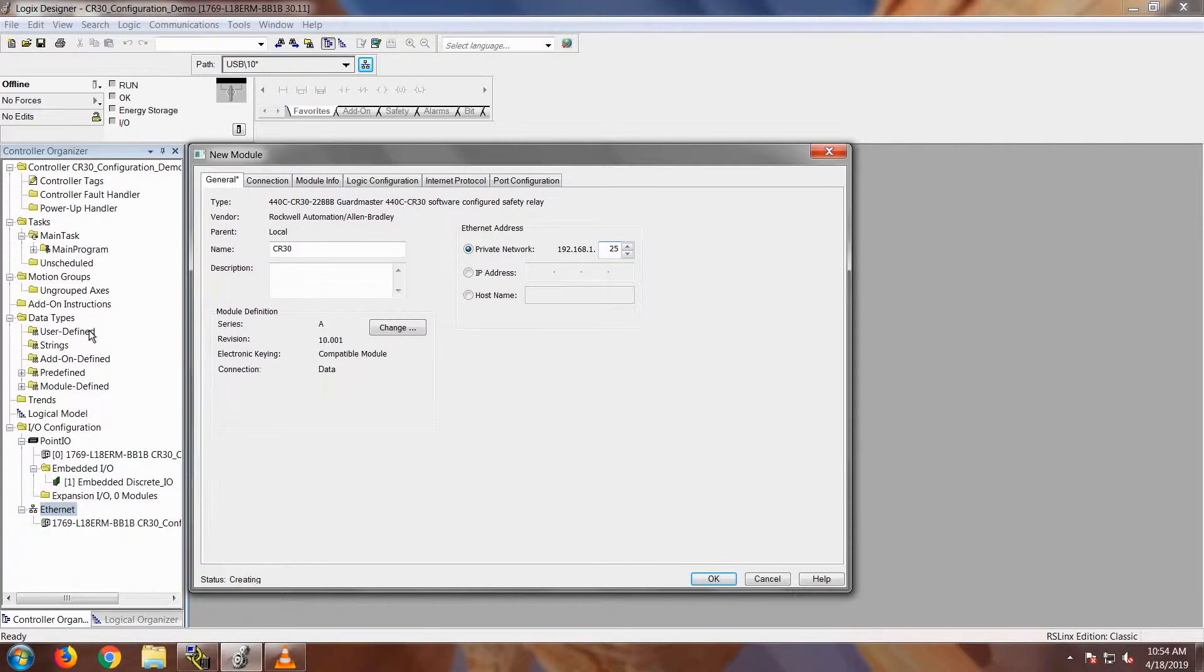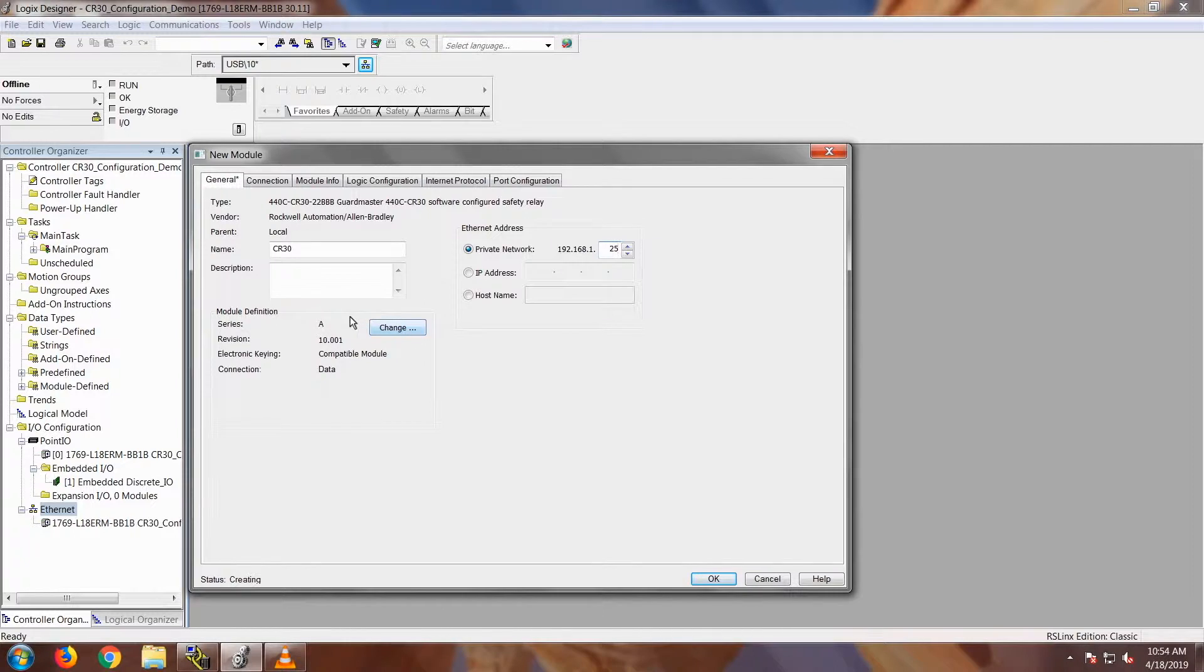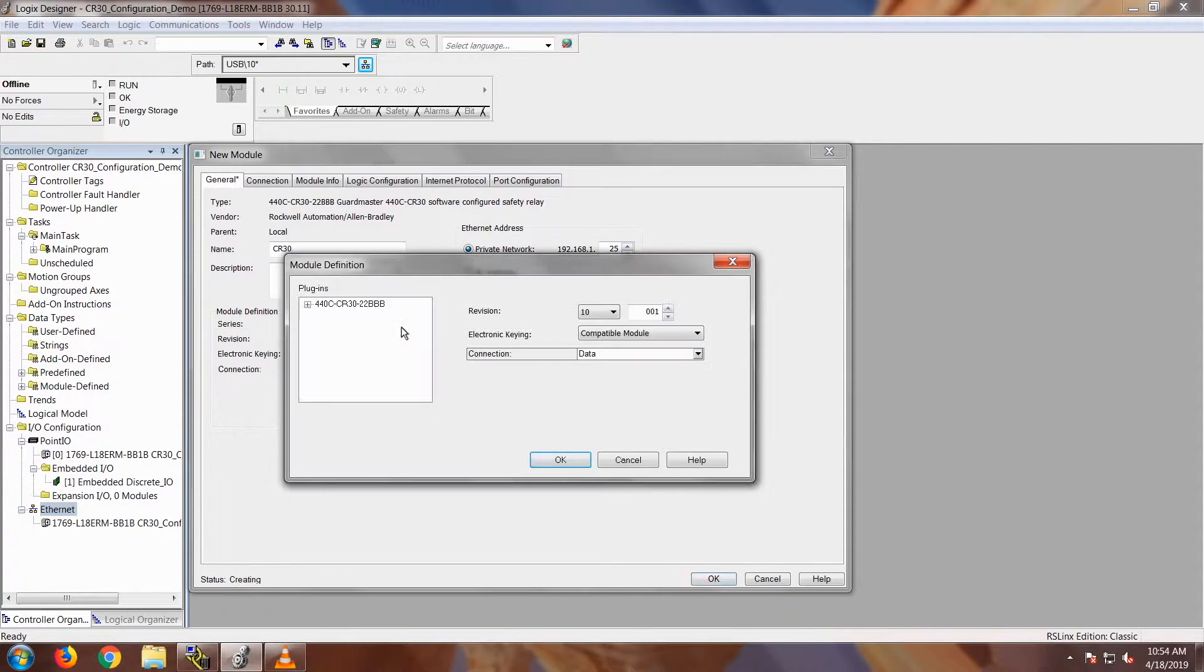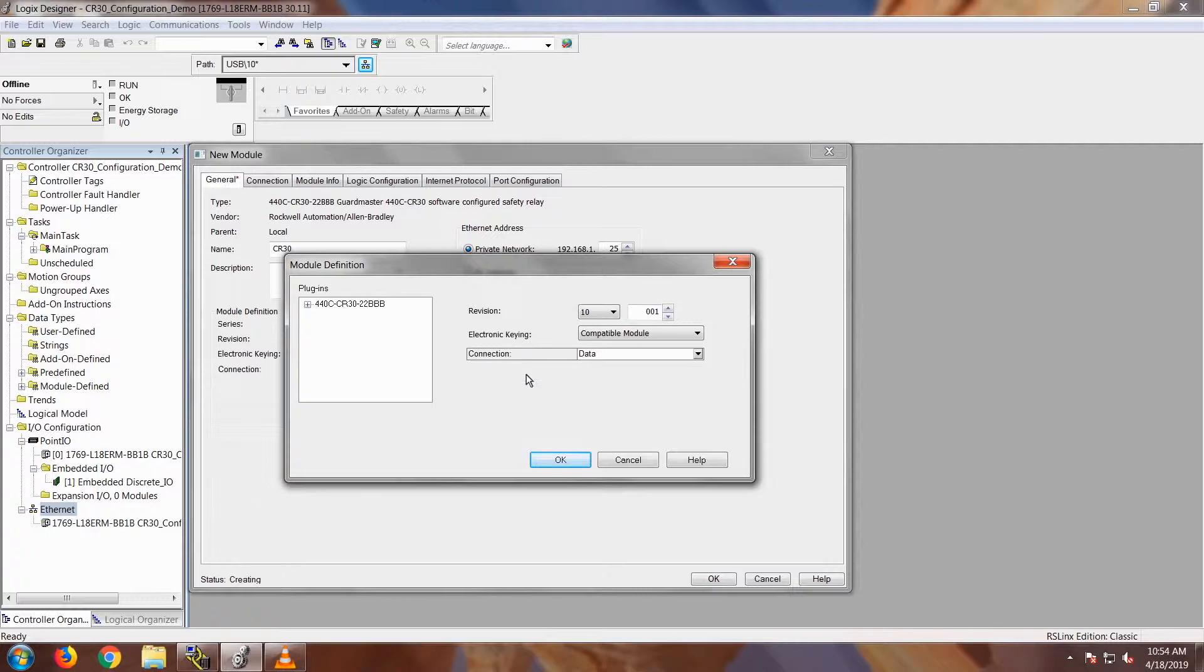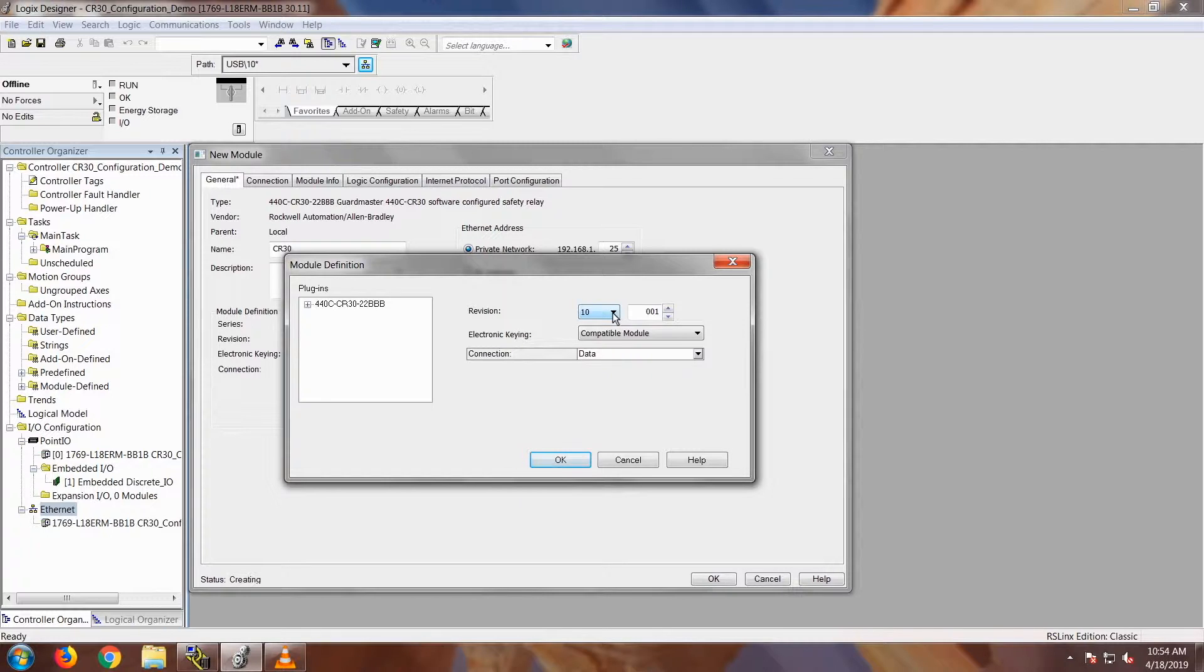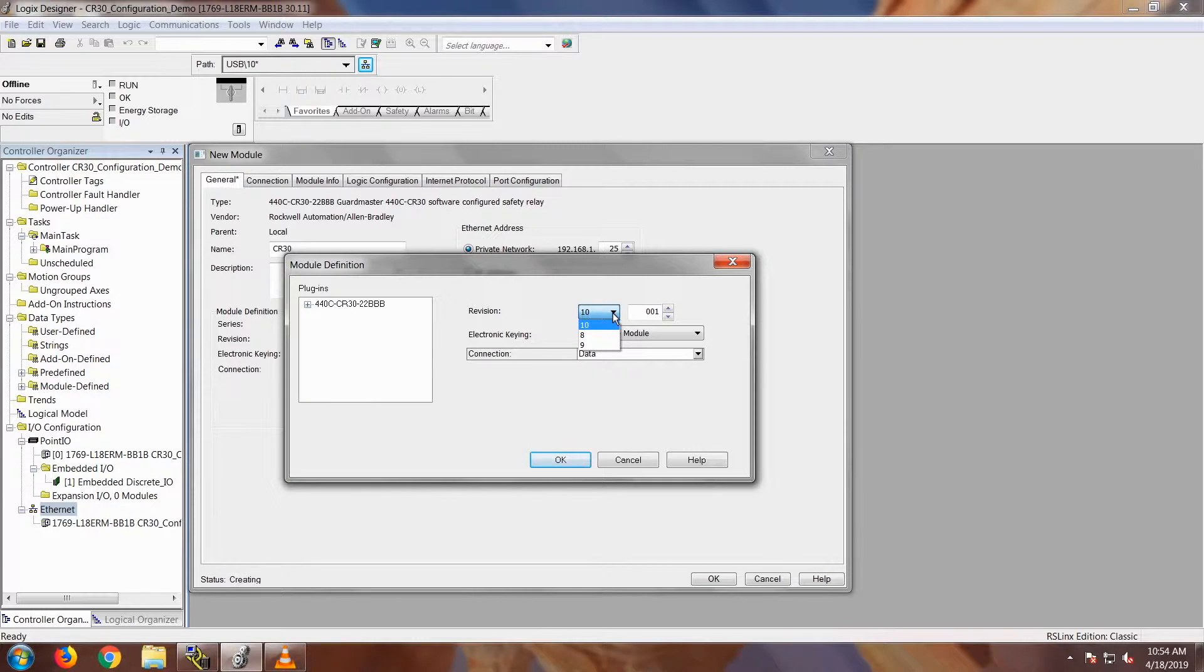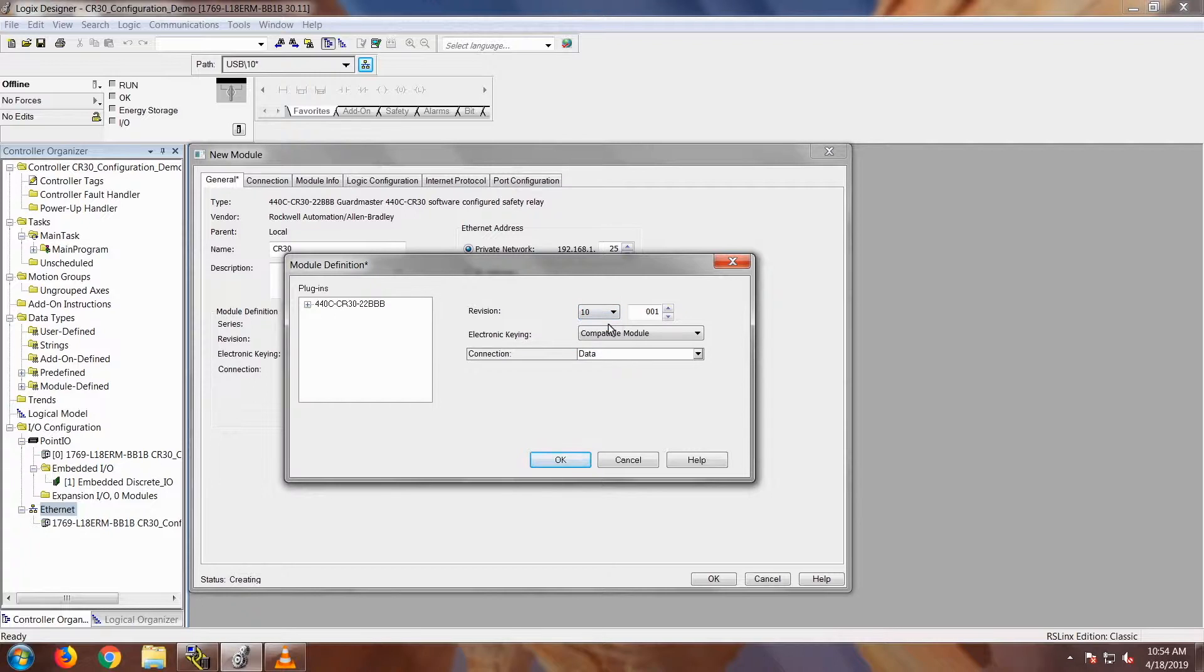You'll notice in this add-on profile there is this change button down here on the module definition screen. I'm going to go ahead and click Change right away to set this part up. When I click Change, this is where you can select your revision, electronic keying or your connection. I'm going to keep my revision on revision 10 because that's where my CR30 and my demo is set at. But the add-on profile does work for revisions 8, 9 or 10, so I'm just going to leave it at revision 10.